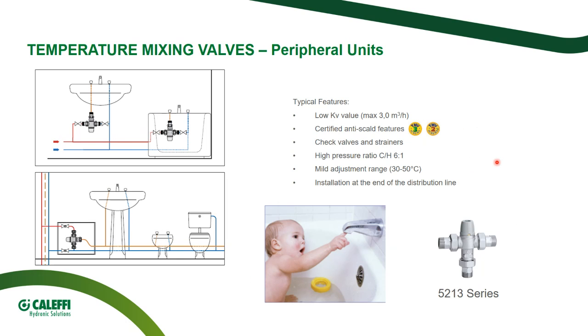Let's go to the other family of thermostatic mixing valve, the peripheral units to be installed at the point of use. They are always three-way valves, but their features are completely different. The Kv value is very low, so they were engineered to manage low flows. I mean, the flow of a washroom, if not the flow of a single faucet or shower. They are certified by a third party with the anti-scald feature. So I reported TMV3 and TMV2, but they can also be ASSE certified for protection from scalding.